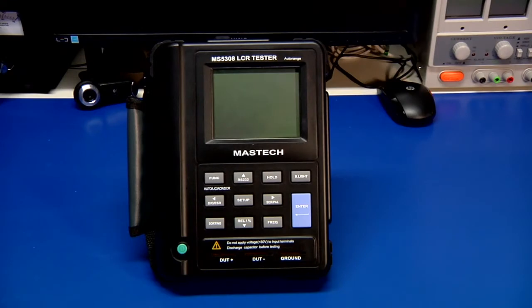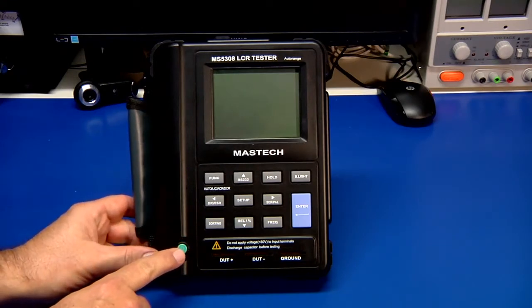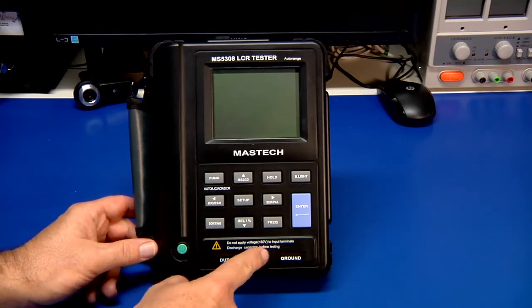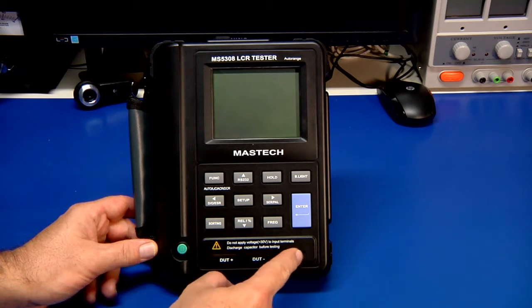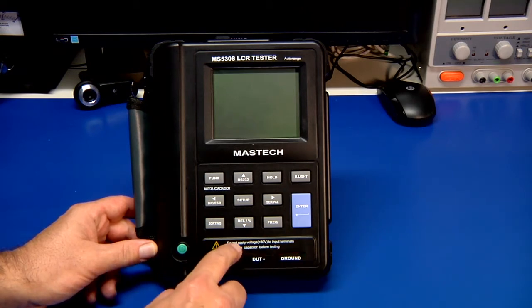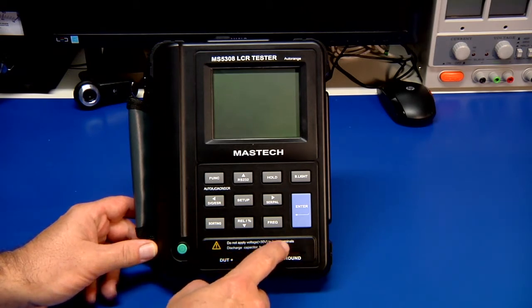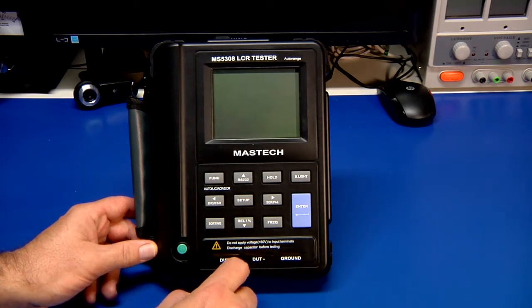Okay, here's the front of the unit. We have our power button over here. We have our Kelvin 4-wire system, and again with a grounded shielding. They also say do not apply voltages greater than 30 volts to input terminals, and discharge capacitors before testing.